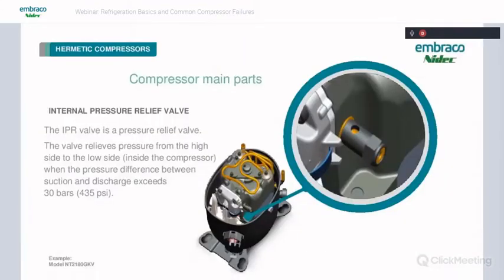So one of the other items we have in our compressors, it's not in every compressor, it's mostly in the 404A commercial compressors that run a little bit higher discharge pressures, is an internal pressure relief valve, and it's a passive high pressure safety that protects the valves in the compressor from a very high discharge situation. Anytime you have a pressure differential between the suction and discharge that exceeds 435 psi, this valve is going to open and relieve that pressure to the low side inside the compressor shell.